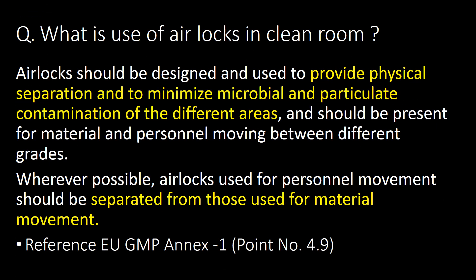What is the use of airlocks in clean rooms? Airlocks should be designed and used to provide physical separation and to minimize microbial and particulate contamination of the different areas, and should be present for material and personnel moving between different grades. Wherever possible, airlocks used for personnel movement should be separated from those used for material movement. Reference: EU GMP Annex 1, Point No. 4.9.